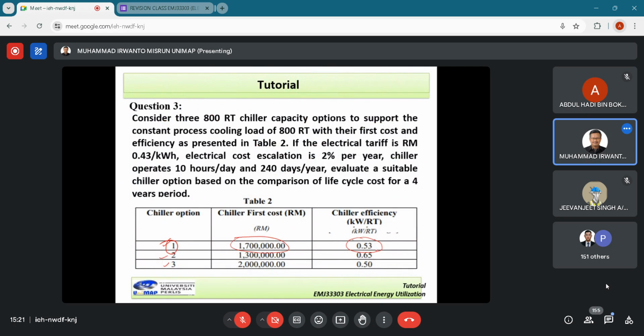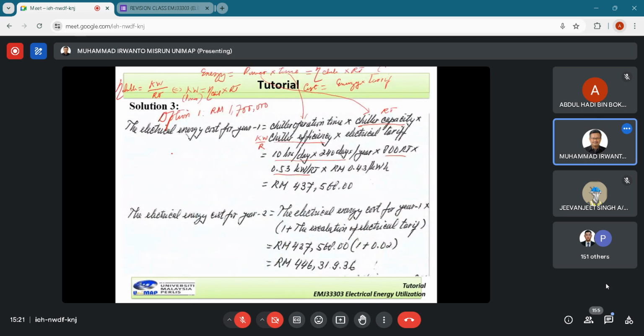Efficiency is 0.53 kilowatt per RT, and tariff 0.43 RM per kilowatt hour. Multiplying by 0.43 RM per kilowatt hour, we obtain RM 437,568. This is the electrical energy cost for the first year.